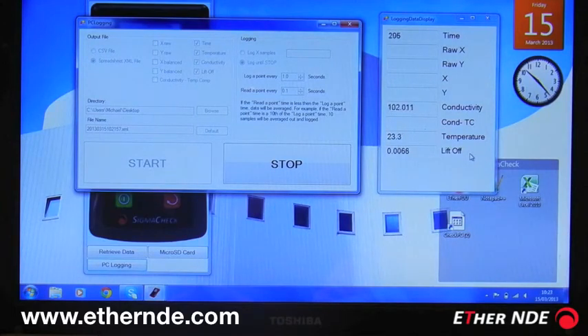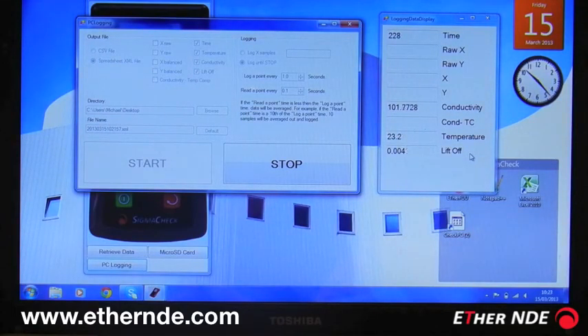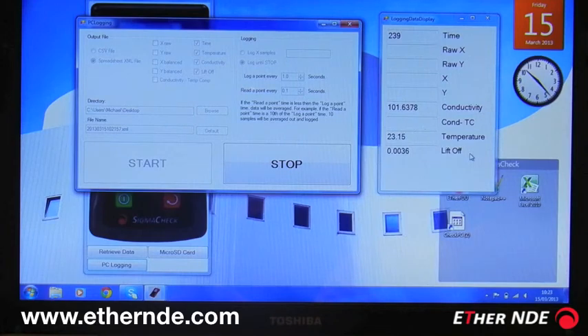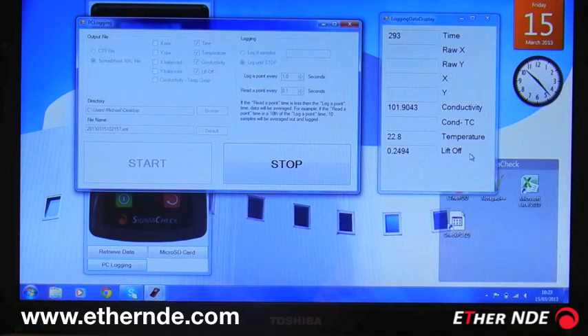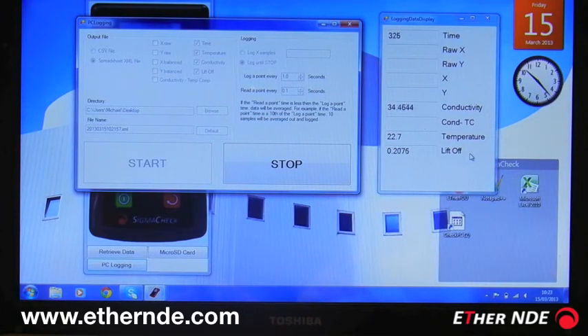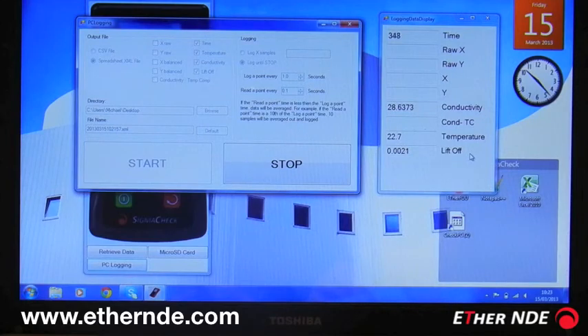If I now go around some conductivity blocks, I'm holding on a copper of approximately 100% IACS. If I slowly lift the probe away, see the liftoff value increasing. I'll go around with a few blocks to get some different values.